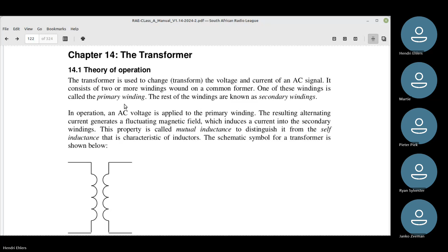Now, between the primary side and the secondary side, there's a ratio, and that ratio is directly proportional to the voltage. So if you have a transformer with, say, for argument's sake, one wound on the primary side and two winds on the secondary side, it will be a step up transformer because the secondary side's voltage is higher than the primary side, and vice versa. If you have a transformer with, say, 20 on the primary and 10 on the secondary, it would be a step down transformer because the secondary side has less than the primary side.